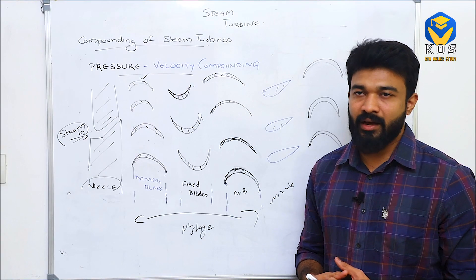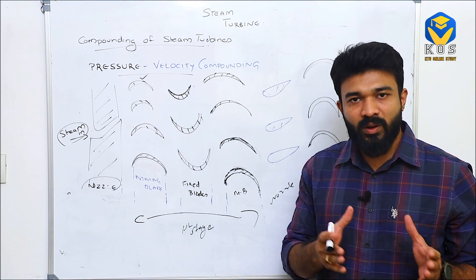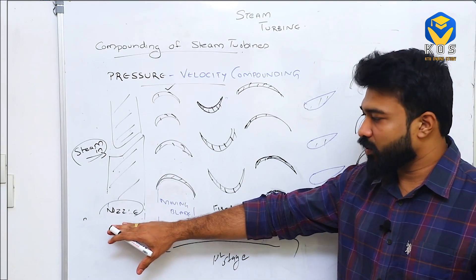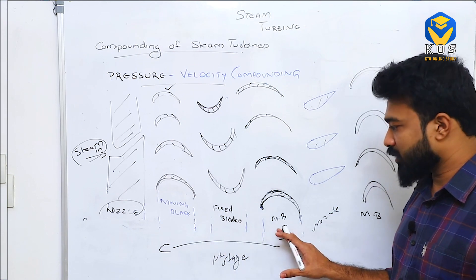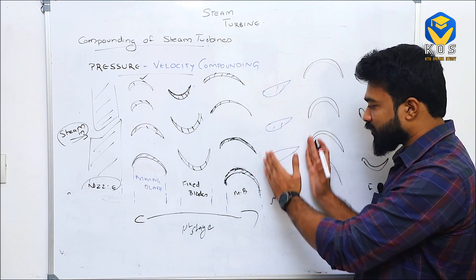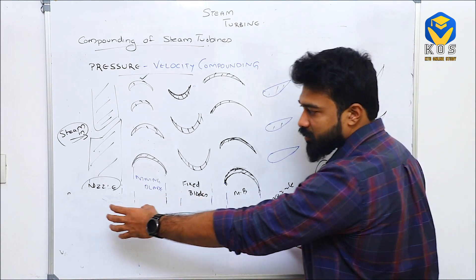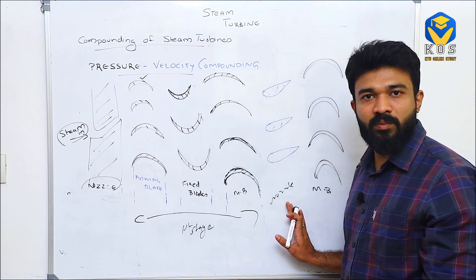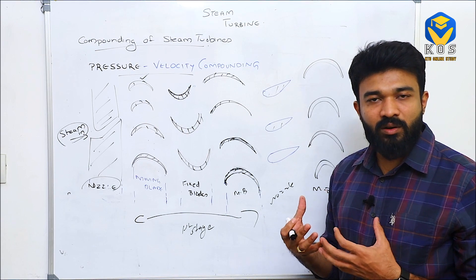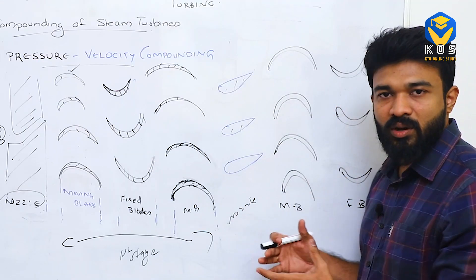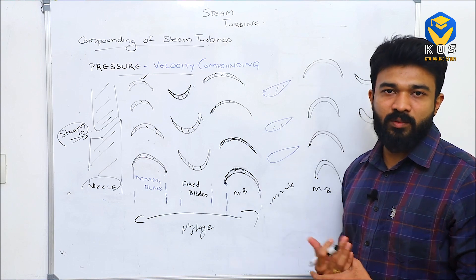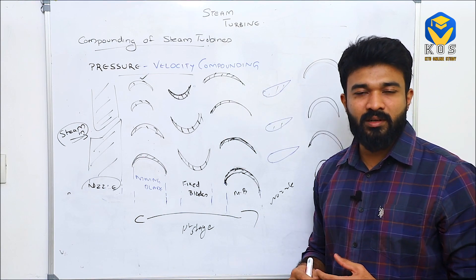One more compounding method is pressure-velocity compounding, which is a combination of velocity compounding and pressure compounding. In this method, velocity compounding takes place first — moving blade, fixed blade, moving blade. Then nozzles are placed before the next stage to expand the remaining pressure and boost velocity again. Then velocity compounding continues with another set of moving blade, fixed blade, moving blade. This type of compounding is called pressure-velocity compounding.